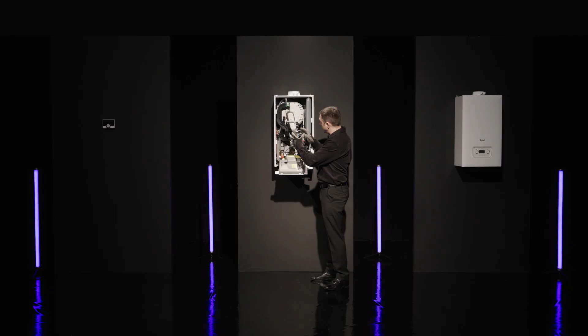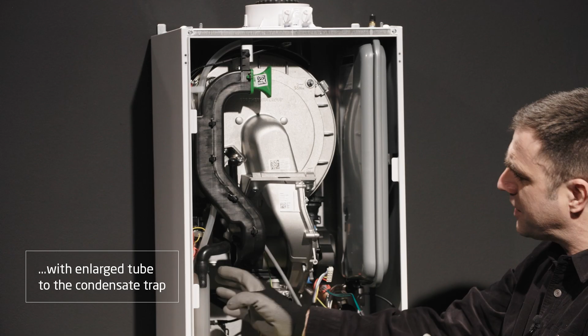Okay, so looking inside the boiler, what you can see is compact, yes, but there's lots of room to get in there and work. There's no problem accessing any components. If I come from the top, what we have is our rainwater drip tray. Any rainwater coming in the air intake is going to collect in there and not get into the boiler and damage it. You can see on here, we've enlarged the tube, which means that any water that comes down will easily get down into my condensate trap, where it can be disposed of down the drain nice and safely.